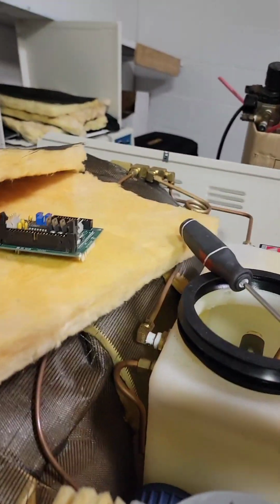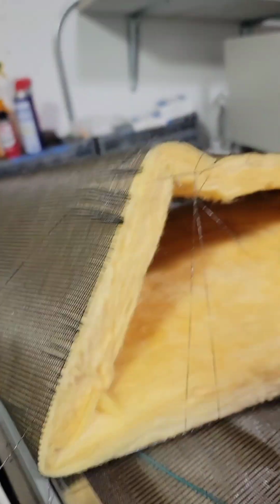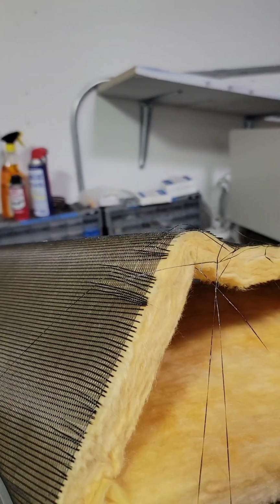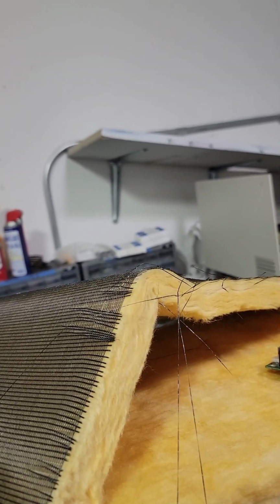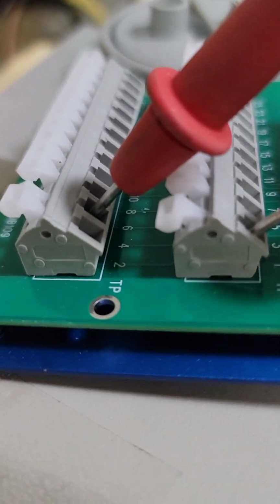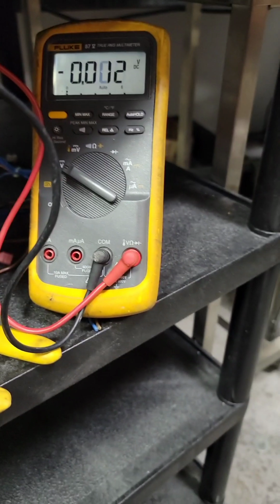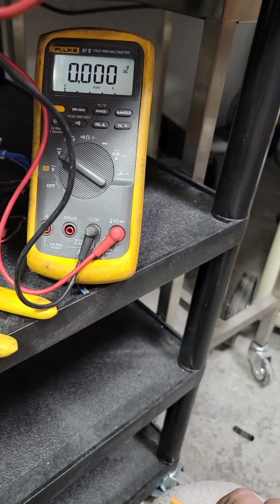So the next test is going to be our pressure calibration. Now, you're going to move this test probe from test point 7 to test point 4. Here we go. So now we're in 4, and this is where we use the next pot. All right, so for the pressure now, we're at 1 and 4. We're looking for 500 millivolts. Clearly not there. So that's going to be pot 2, the top one right here.